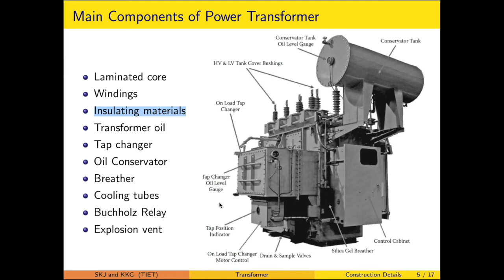The transformer core, as shown here, is made of laminated structures. Lamination means thin sheets. The objective is to reduce the eddy currents. In a solid structure, the eddy currents are confined to a large area. Because of the thin laminations, the eddy currents are confined to a smaller area. Because of this smaller area, the resistance to the eddy current increases, which leads to a reduction in the eddy current's value and in the eddy current losses. So that is one aspect.